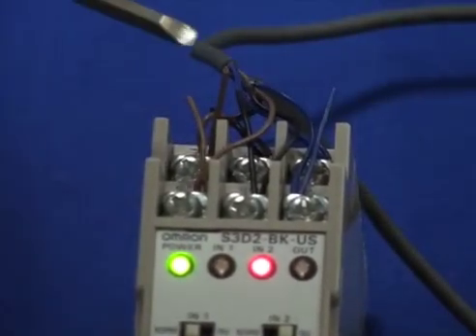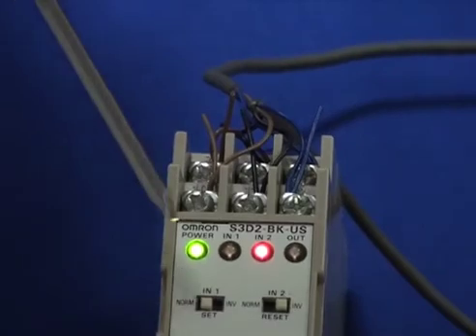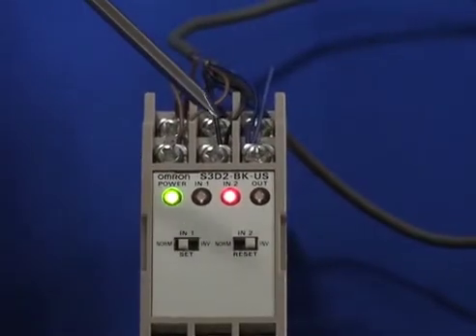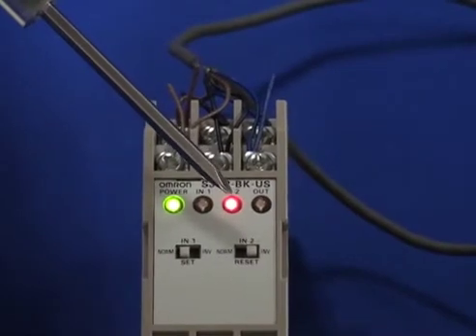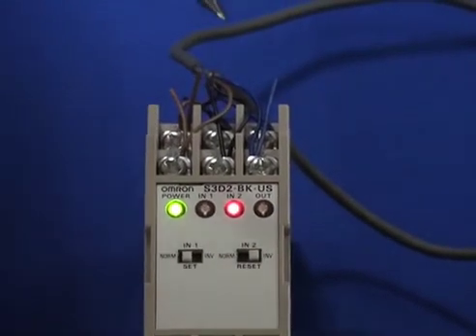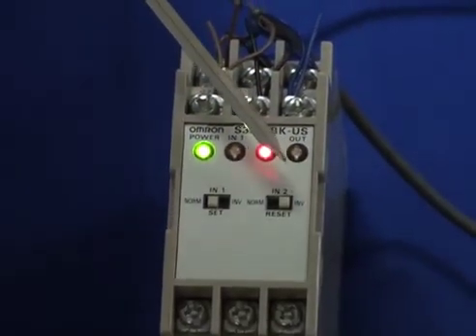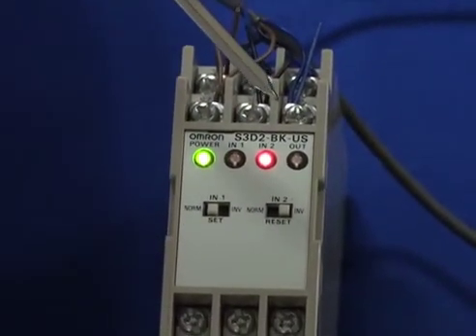Once you have your two sensors connected, then you need to set your logic dip switches. This is switch one and this is switch number two, and in this case of liquid level control, input two needs to be inverted for the logic to work properly.